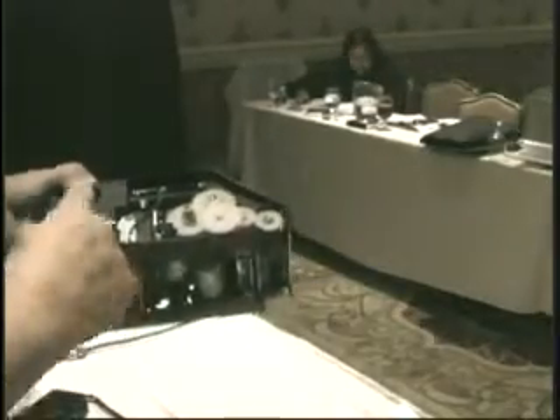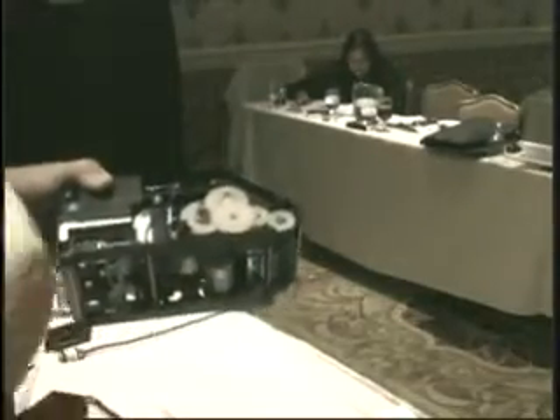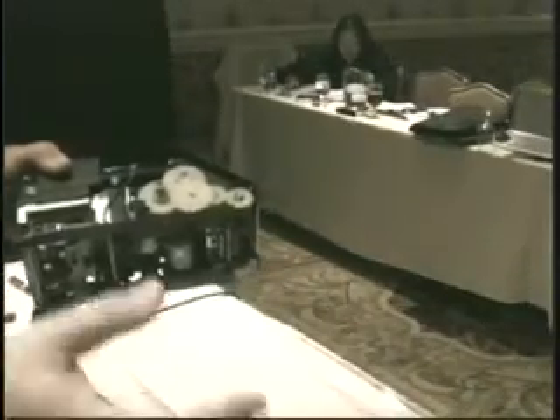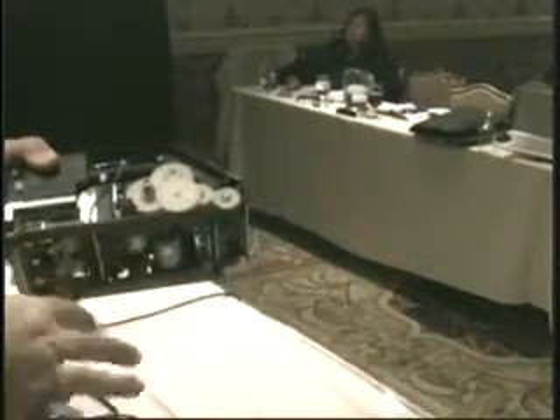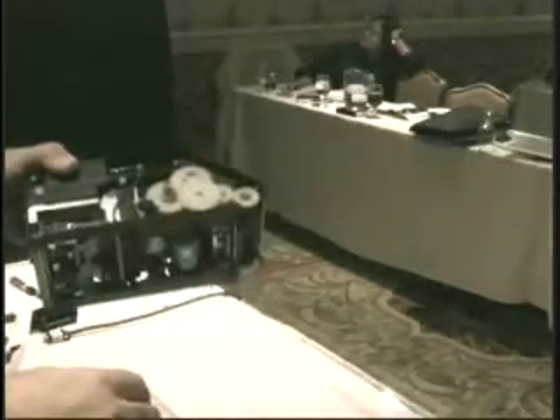Okay, so that's the motor test. Instead of dip switch 1, if you use number 2, it'll run the motor test in reverse. Same thing - it's just running the motor to make sure it's within tolerance speed, but in both directions, because it's a brush type motor and you want to make sure you don't have a brush that's cracked or causing problems.